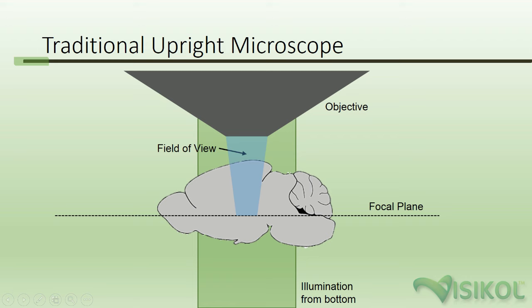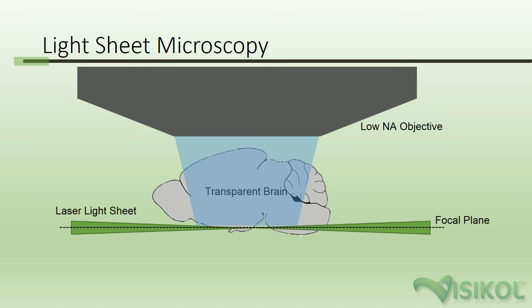To understand how light sheet microscopy works, it's important to understand why traditional microscopy does not work for imaging whole, cleared, and labeled tissues. If you were to take a cleared and fluorescently labeled mouse brain and place it on an upright microscope, the light source will excite the fluorophores throughout the entire depth of the tissue. This will result in a bright and blurry image where signal well outside of your objective's focal plane severely alters your image.